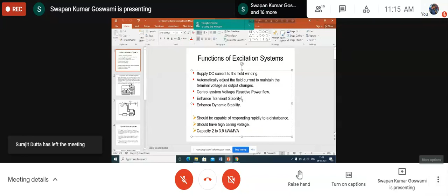Now, it enhances transient stability. While discussing the methods for improving the transient stability, I have mentioned this. If you want to control the transient stability, a good method is also to control the excitation voltage, the field current, because as you control the field current, the generated voltage is changing. Depending upon the requirement, you may increase or decrease the generated voltage. That means you may increase the peak of the power angle curve and you may decrease the peak of the power angle curve.